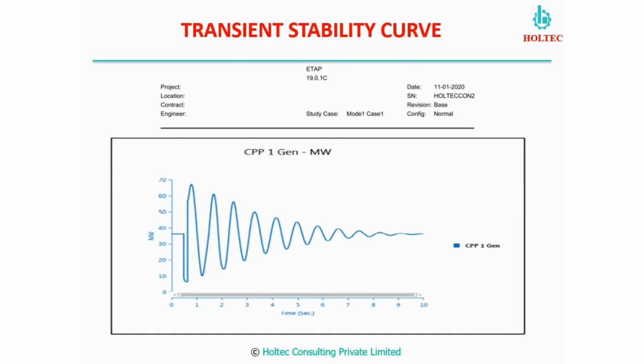So in that way, if we check, this will give us assurance, but nothing will be 100%. There will be some chances. Even after that assurance there can be a possibility, because 100% cannot be achieved in any study. There can be 1%, 2%, 3% chances that in very abnormal conditions there will be a loss of stability. It may be because of our study errors, or because of the operational speed of the fault clearing system, maybe relay sluggishness, maybe breaker sluggishness. This may matter because here we are talking of 100 milliseconds or 150 milliseconds.